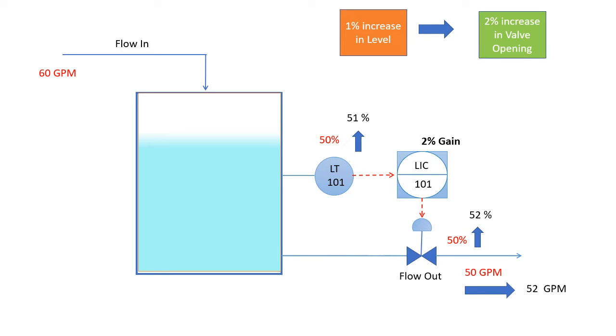As a result, the flow will increase to 52 GPM. Still the flow at the outlet is less than the flow at the inlet, so level is still raising. Suppose the level increased to 55 percent. At this moment, the output of the valve should be 60 percent leading the flow to 60 GPM. At this moment, inlet flow is equal to outlet flow, so there is no further increase or decrease in the level.